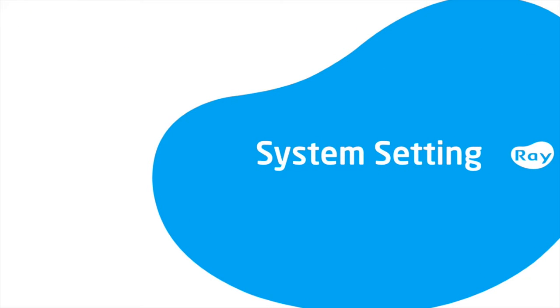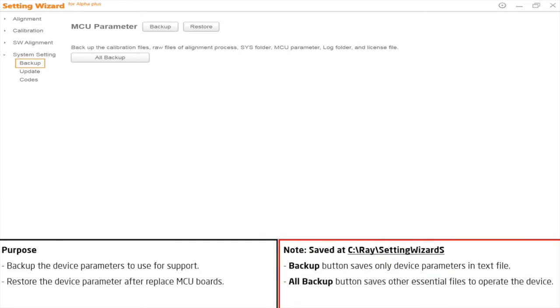RAY recommends backing up all data after a new installation, so you can prepare for technical support in the future. Also, you will back up the MCU parameters before replacing the MCU. The Backup button saves only device parameters in a text file at C drive, RAY folder, SettingWizardS. To restore the data to the new MCU, simply click the Restore button.